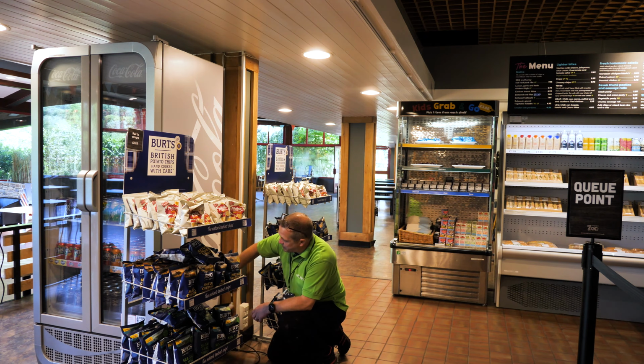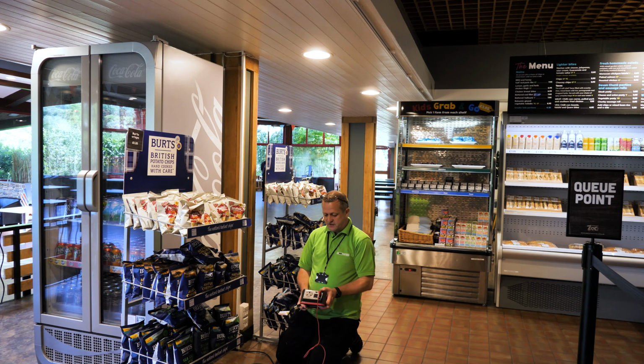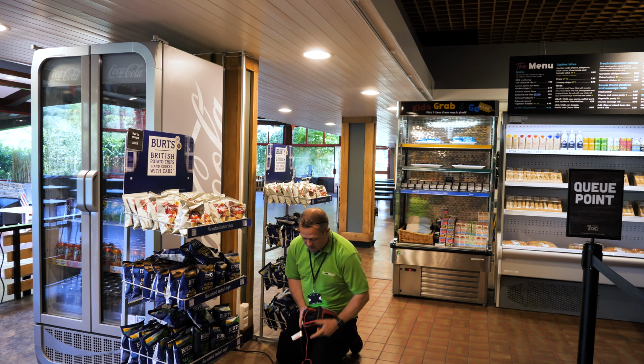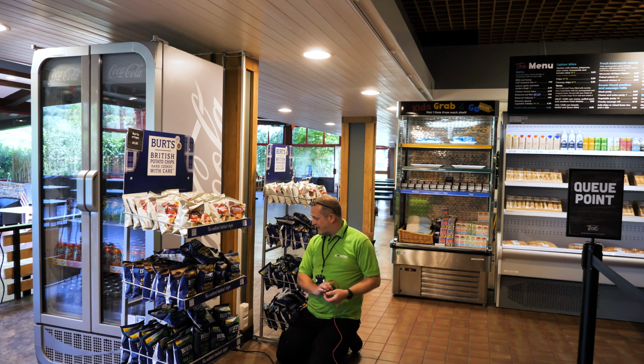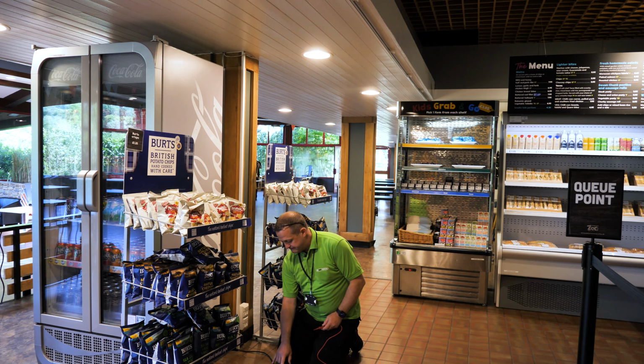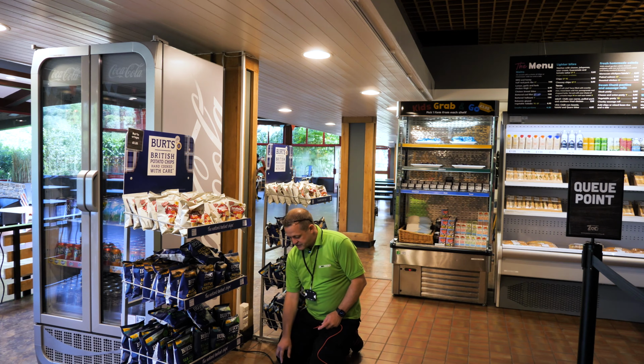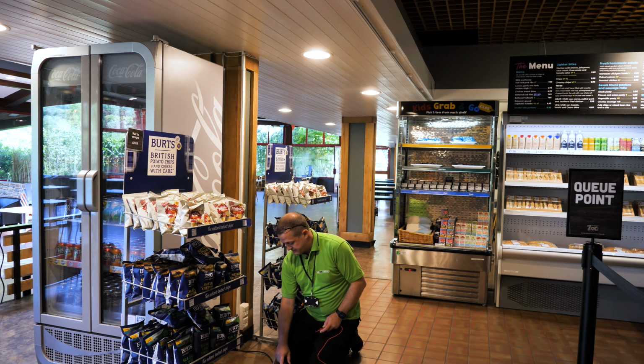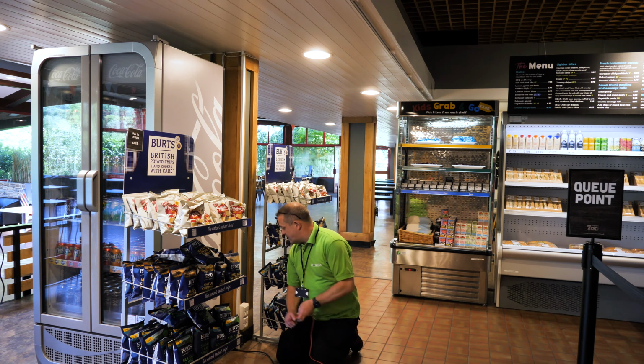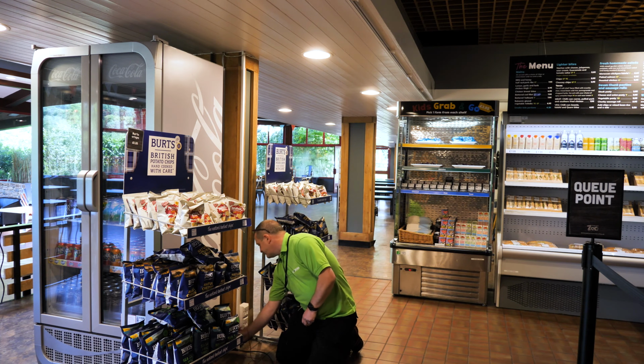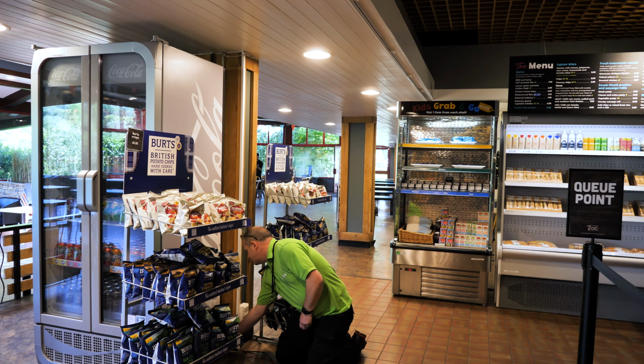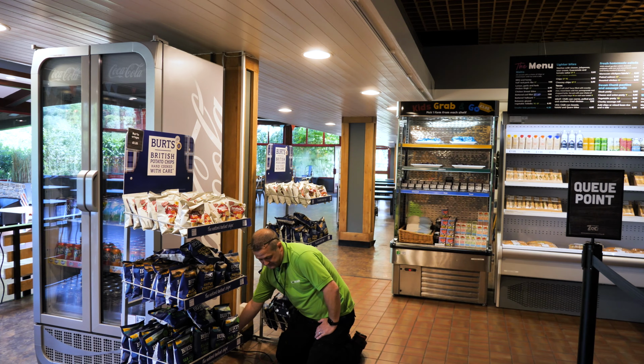So I'm going to take the plug out, put it into the PAT testing machine once the machine has switched itself back on, and effectively what we're going to do is a class 1 test. So I'm going to select the correct test on the machine, and then we're going to find some exposed metal parts. What I'm going to do is use a screw stud just down here, and then we're going to go through the test. And that's showing a good earth reading of 0.01 and an insulation of over 20. So that test is complete.